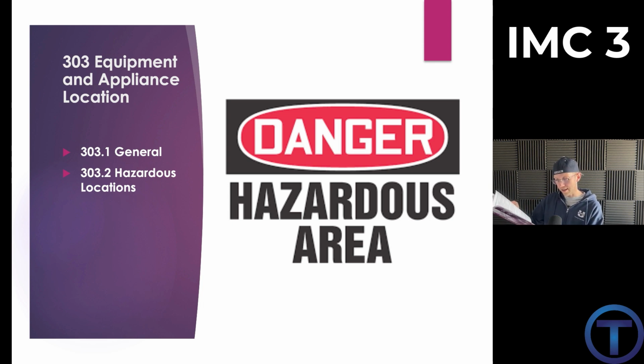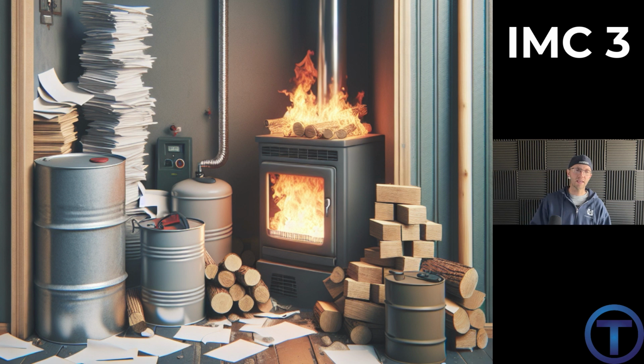Hazardous location is any location considered to be a fire hazard for flammable vapors, dust, combustible fibers, or other highly combustible substances. The location is not necessarily categorized in the building code as a high hazard use group classification. So it's basically saying, if there's a higher chance of things catching on fire, then that's a hazard. And let's not put a flame producing appliance into that highly combustible location. Perfect.